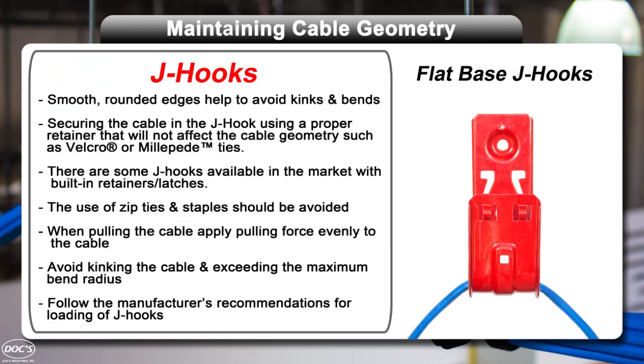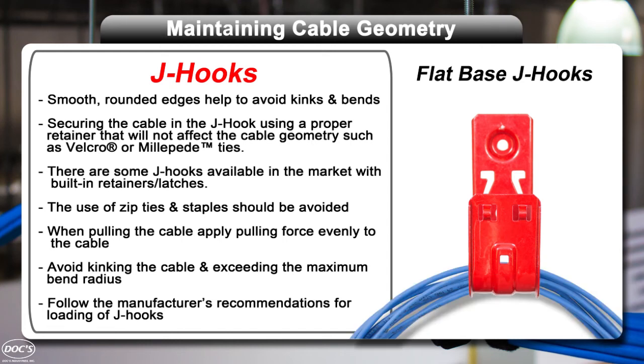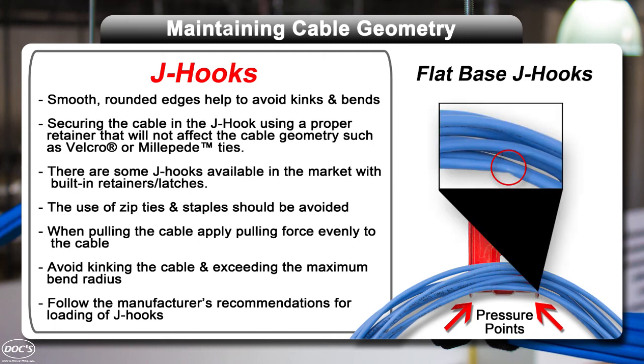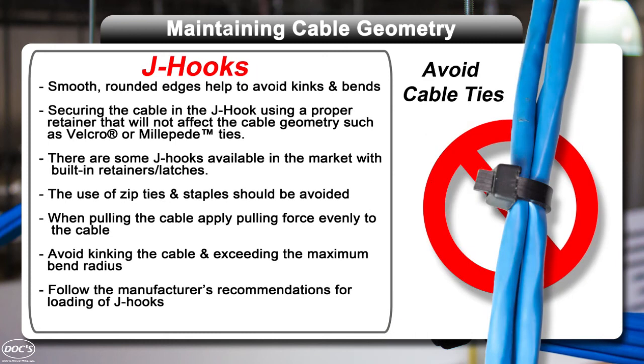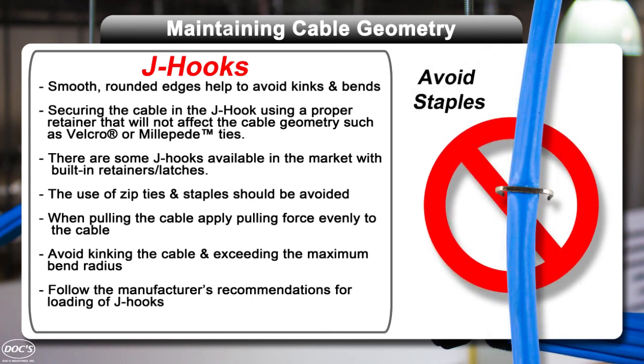A cable support with a flat base tends to cause an abrupt bend compared to a hook with a beveled or rounded base. A flat-based hook can create pressure points that can change the geometry of the cable. This is easier to see with a single cable versus a bundle of cables, but the pressure point is always there. When you bundle cables together, they have an inherent stiffness that tends to prevent tight turns, but not these pressure points. Avoid situations that tend to kink or change the geometry of the cable, such as tightly cinched cable ties, staples, or knots.